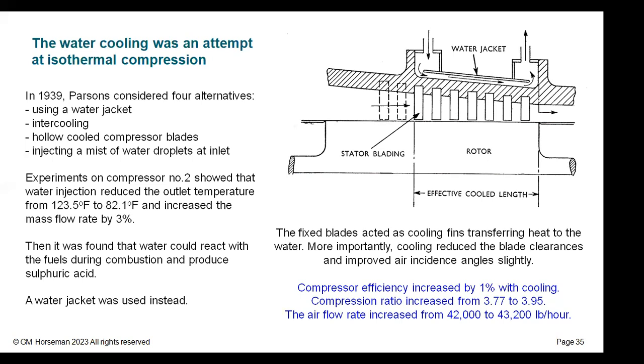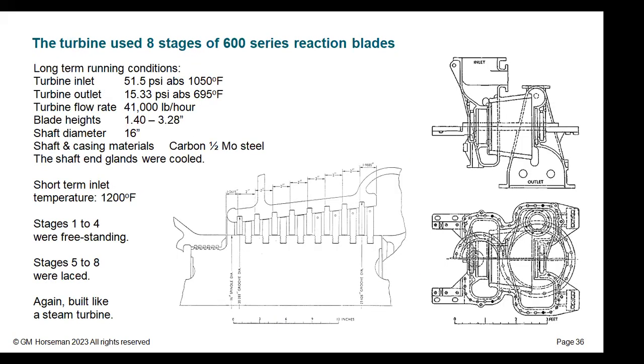Just that water jacket improved the compressor efficiency by 1%, as well as boosting the compression ratio and the airflow rate. So it was quite a useful thing. But there are consequences, so please bear that in mind, and we're going to come back to that in a couple of slides' time. This is the turbine casing. It's an 8-stage turbine. The first 4 stages were freestanding, and the last 4 had lacing wires to make sure the blade vibration characteristics were good.